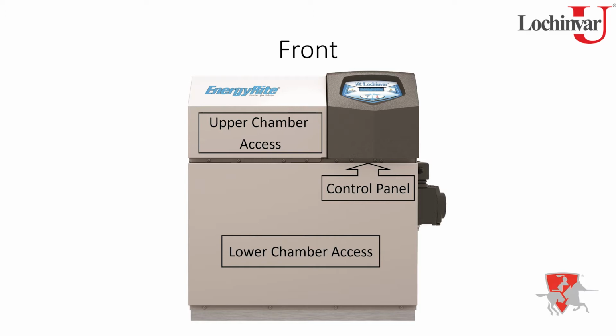One of the things that they did with the second generation is you can see that split in the middle there. Before, what you had was overlapping panels, and when you took the top panel off, it also removed all the screws from the lower panel. So whenever the fan started, it would blow out the top of the lower panel and you'd get a little bit of an air leak, which would always throw off your combustion air numbers.